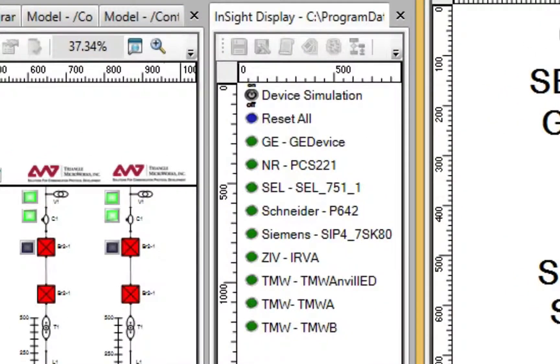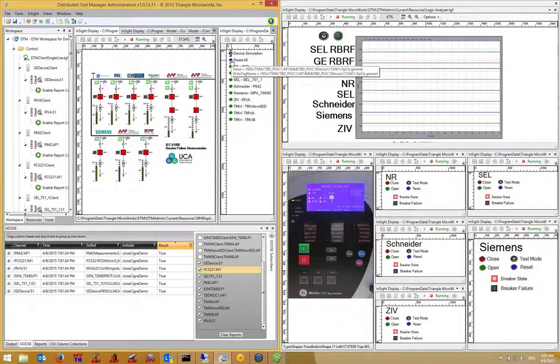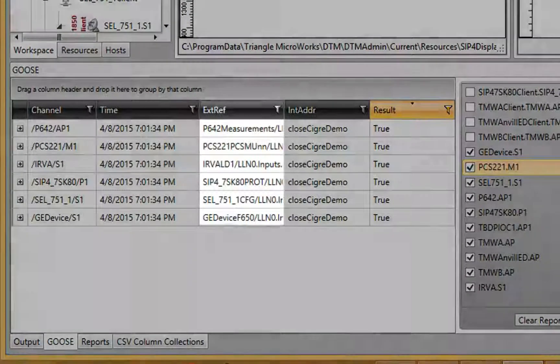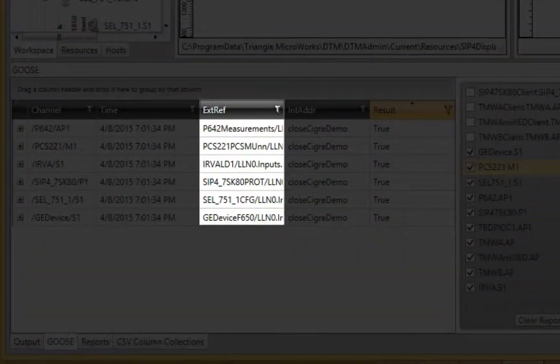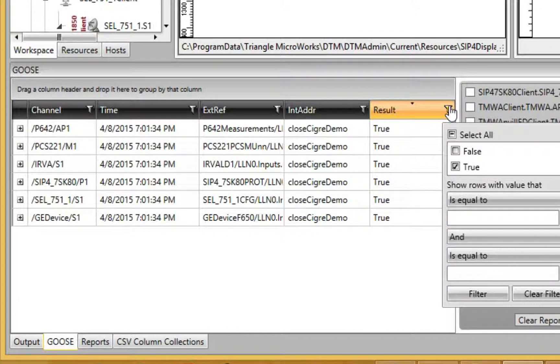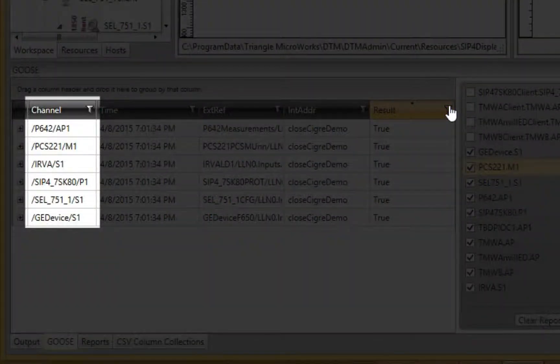Now I'll send the PIOC Reset Goose message to close the breaker and clear test mode in each device. Let's look at the Goose report log for DTM. This report shows the individual external references that were received in a Goose message by each simulated device. Here I filter the log to only show data attributes with the value of true, and we can see that each of the simulated devices received the broadcast message.